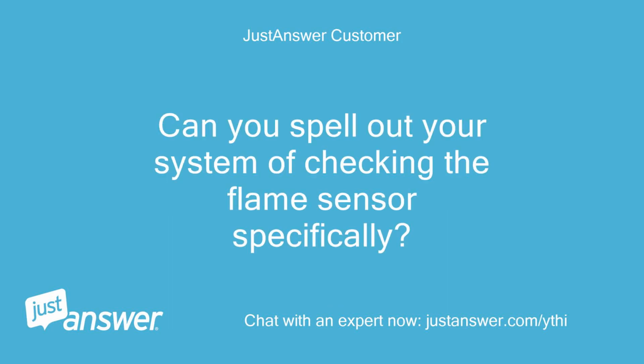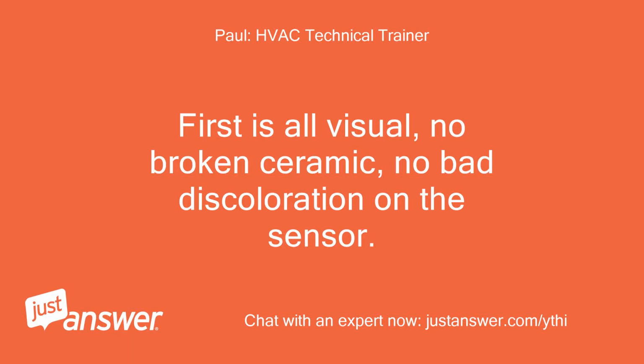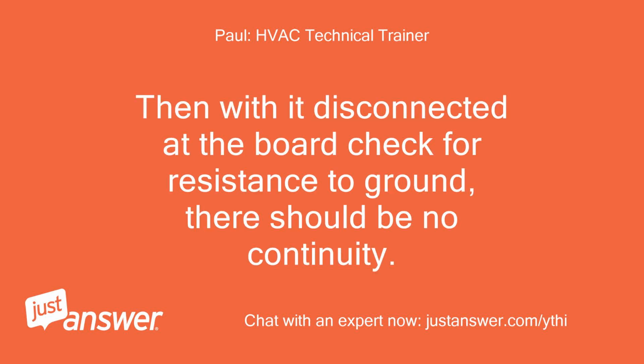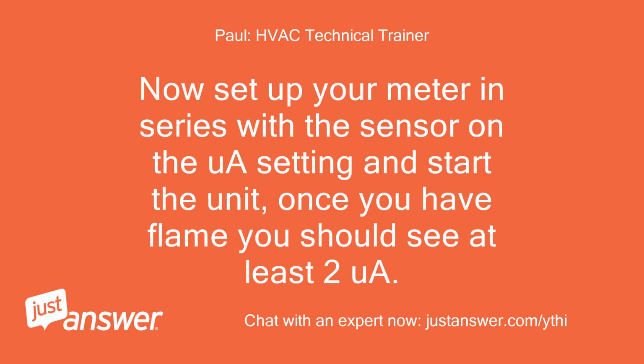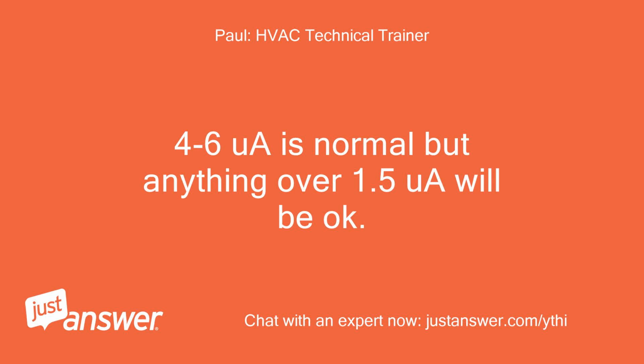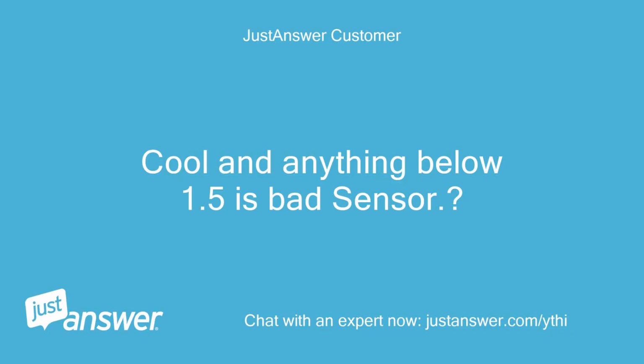Can you spell out your system of checking the flame sensor specifically? First is all visual, no broken ceramic, no bad discoloration on the sensor. Then with it disconnected at the board, check for resistance to ground, there should be no continuity. Now set up your meter in series with the sensor on the UA setting and start the unit. Once you have flame you should see at least 2 microamperes. 4 to 6 microamperes is normal, but anything over 1.5 microamperes will be okay. Cool, and anything below 1.5 is bad sensor.